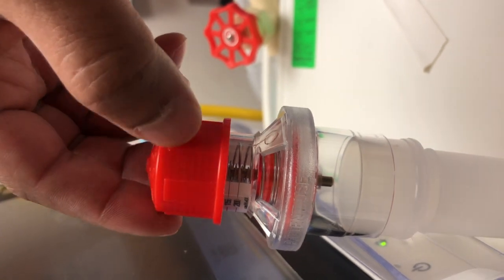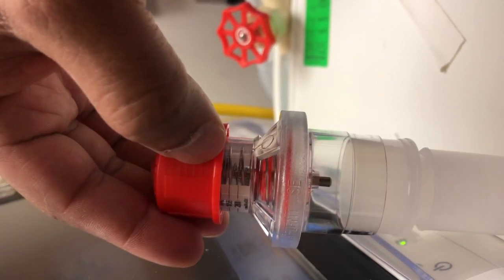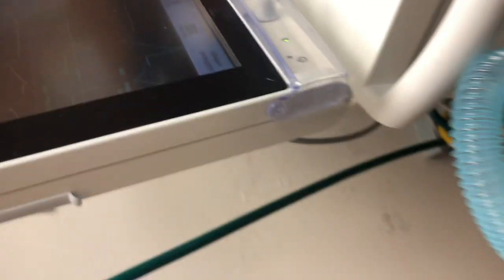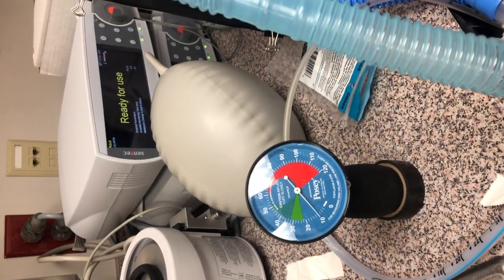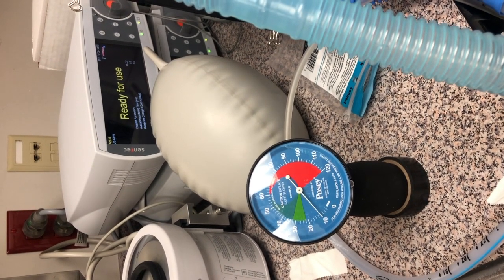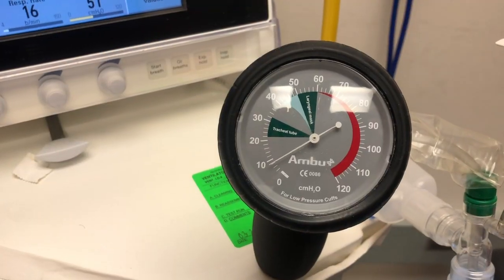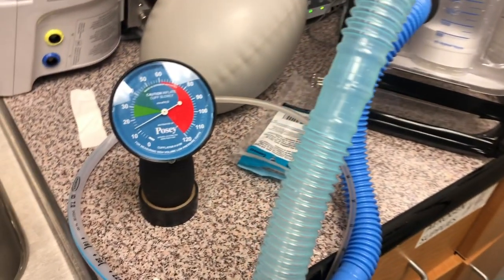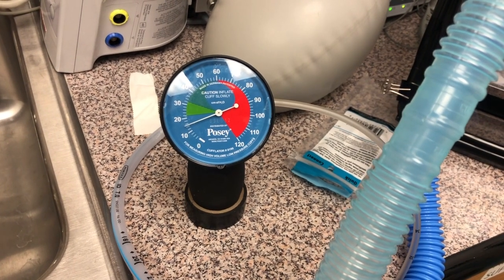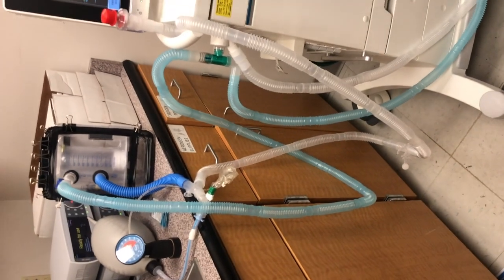Please do note that the smaller the ball valve is, the better the sensitivity, and you'll have a good way to regulate pressure or volume, so it would be preferred. Here I have used a 1/4 inch ball valve, which hooks up directly into the 1/2 inch adapters and does not need any modification. For demonstration I have also shown a bigger ball valve, which serves the same purpose, however is less sensitive, and even a minor variation can cause changes in pressure and volume. Therefore I prefer the smaller valve for safety reasons.